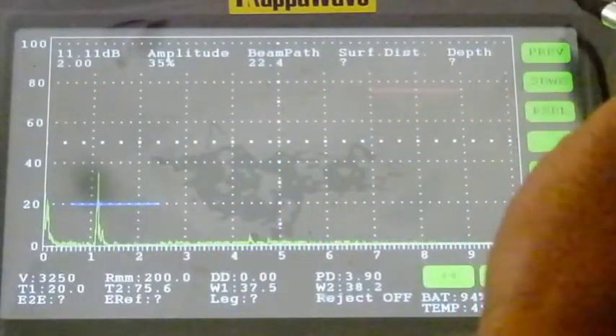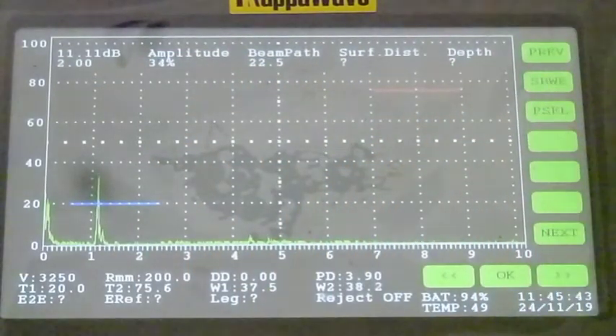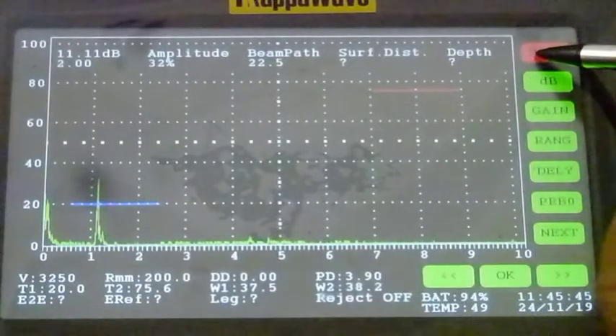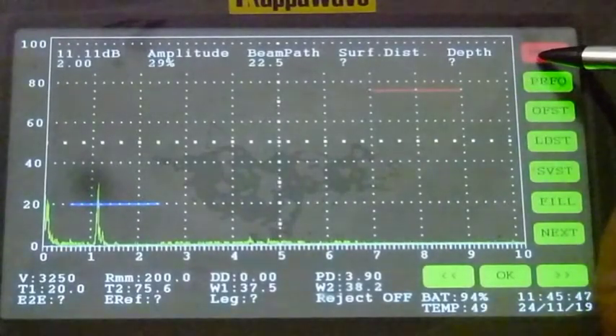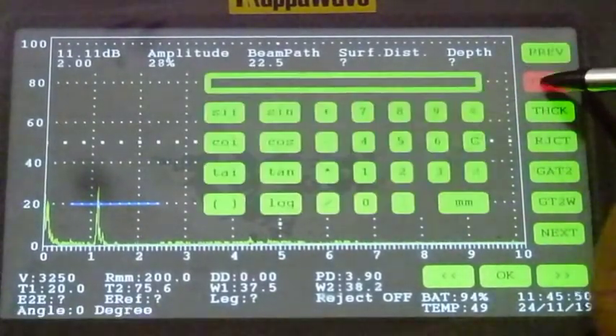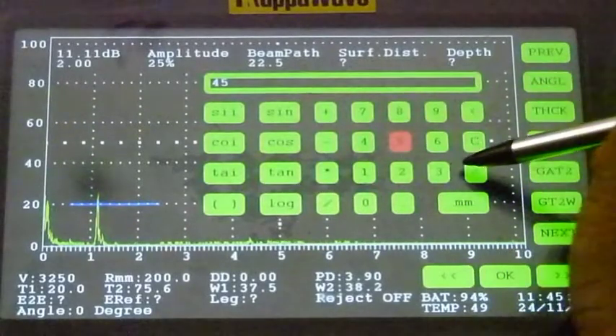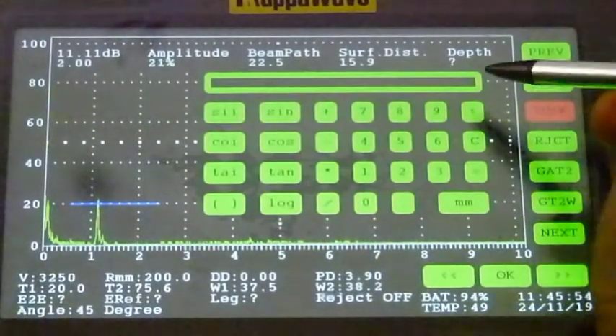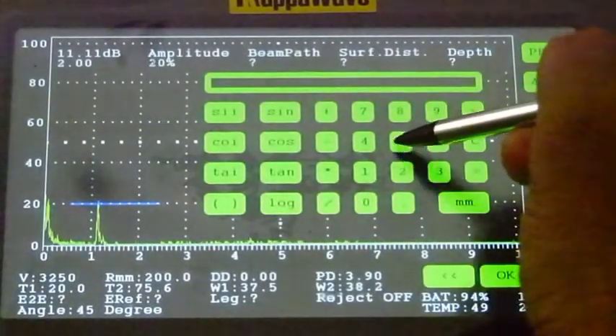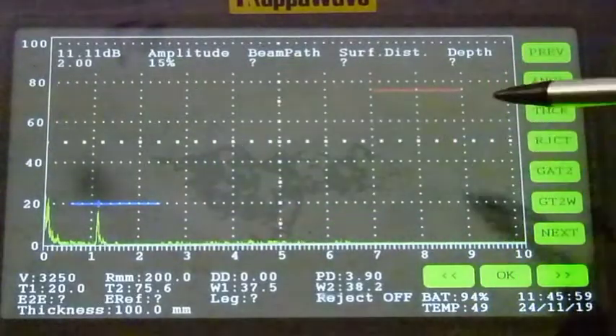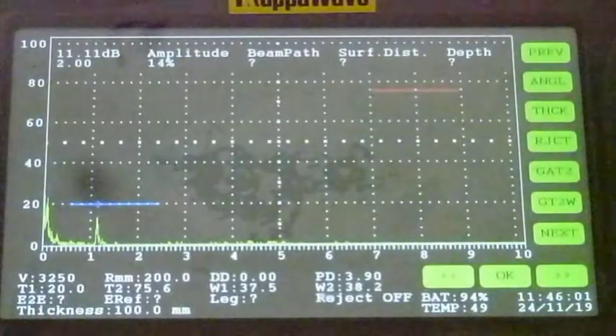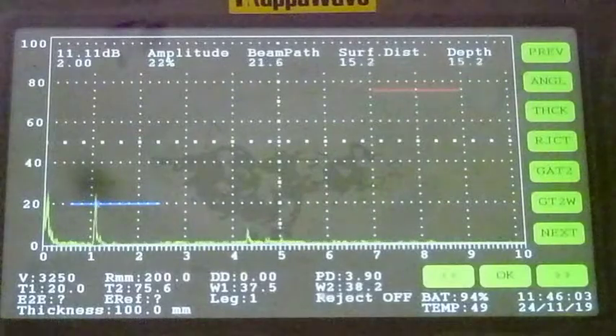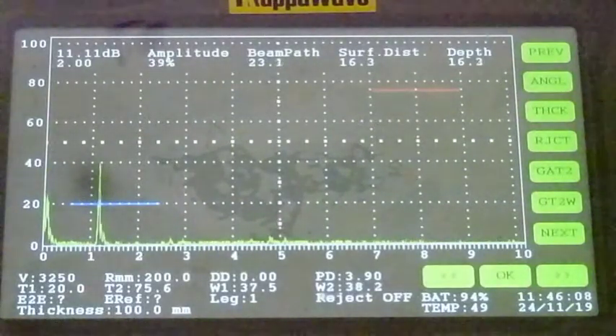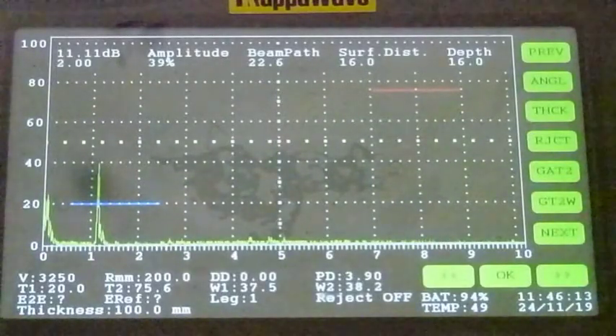Right now the surface distance and depth are not given, and that may be shown once the angle of the probe and the thickness of the test material are entered. Thickness is roughly given as 100 millimeter or so. Now if you pull the probe further back, okay, this is the signal you are getting from the 1.5 mm hole, which is maximized to about 40% in height.